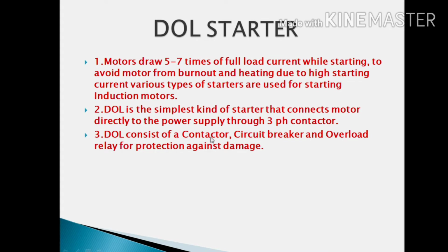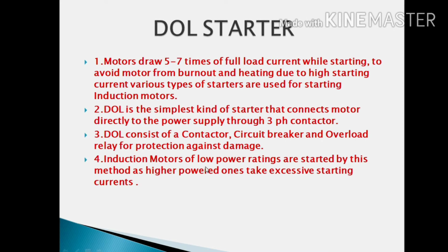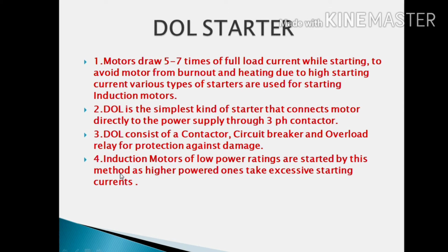The DOL starter consists of a contactor, circuit breaker and overload relay for protection against damage. Induction motors of low power ratings are started by this method, as higher powered ones take excessive starting current. For higher powered ones we have auto transformer and star delta starters. Only low powered motors use the DOL starter, as higher powered ones take higher starting current, so there will be a very high voltage dip. That's why we are not using the DOL starter for higher powered motors.